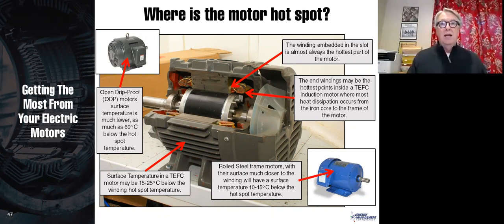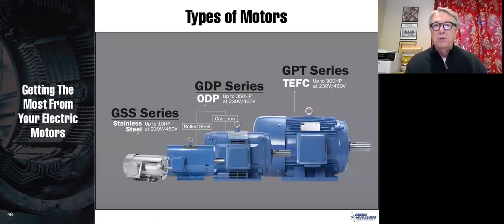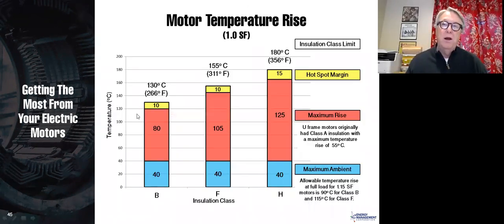So you can actually sense the temperature by using RTDs or thermistors that we will talk about next week. But if you don't know that, then you just want to see if it's too hot. #1, you can put your hand on the outside of a TEFC motor. If you can leave it there for 3 seconds, it's not too hot. I still stand by that. On the other hand, you could take your infrared thermometer, shine it on the outside of there and get an actual temperature on the outside, add 25 degrees to that, and you will know the temperature on the inside, and then you compare that with the insulation temperature here.